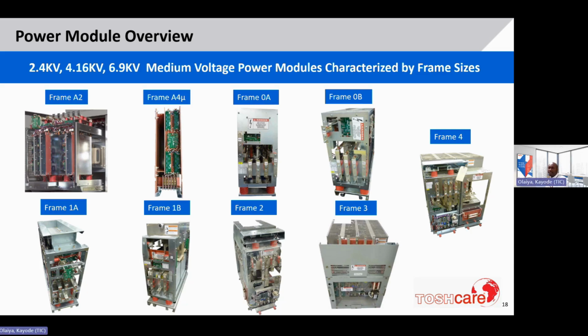The A is the early version and the B is what we manufacture currently, though you can still see both in the field. The difference is in the heat sink and the way the modules are cooled. Same with the frame 1, which is the 4160, but goes up to 2,000 horsepower. There is the A and the B, and you can see the physical differences, and most of that has to do with cooling of the module.